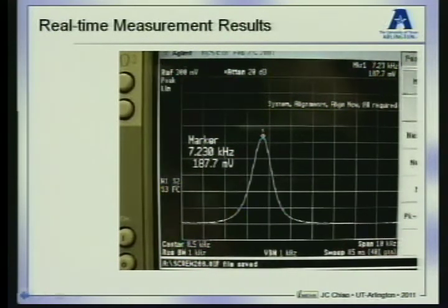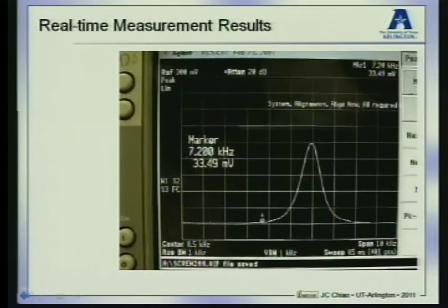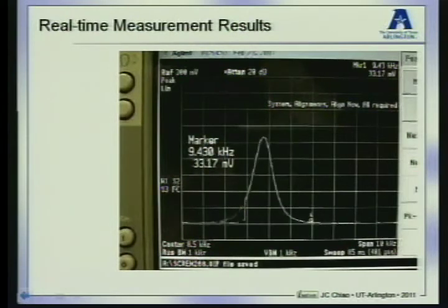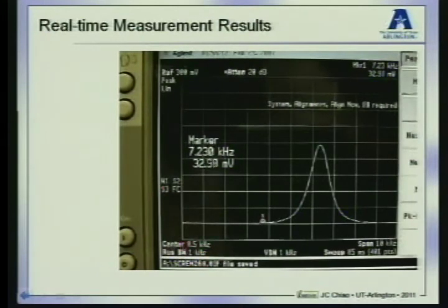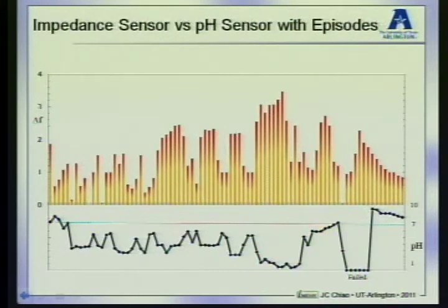As soon as the module is put near the body, it picks up the signal inside the body. This is a baseline of 7.2 kilohertz. Now we fed the animal some water, and you can see the signal drift up to 9.43 kilohertz, which indicates non-acid reflux. As soon as the water left the esophagus, it goes back to baseline. Now we fed the animal some orange juice, which has a pH level of 3, and the signal goes up to 9.8. So by observing this signal, we can see all these episodes in the animal.